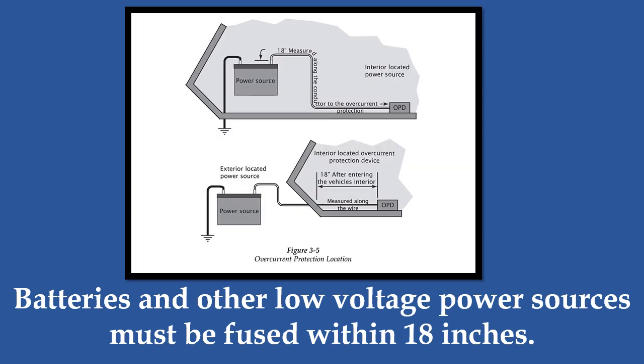When the battery compartment is on the interior of the RV, overcurrent protection still must be within 18 inches, as seen in the top illustration. This measurement is taken along the length of the wire, not in a straight line. When batteries are on the exterior of the RV, say, for example, on the A-frame of the trailer, the overcurrent protection must be within 18 inches of entering the interior of the RV, as seen in the lower illustration.